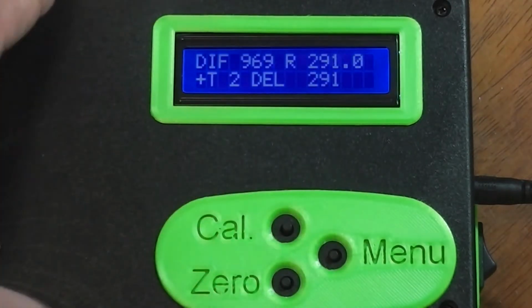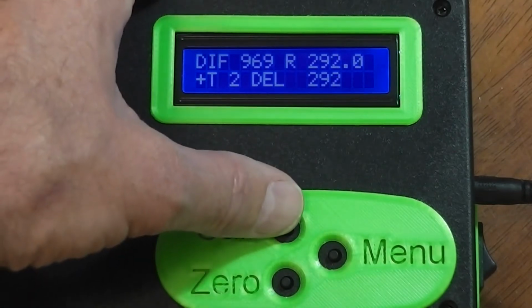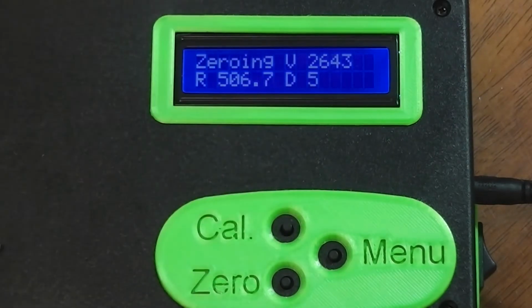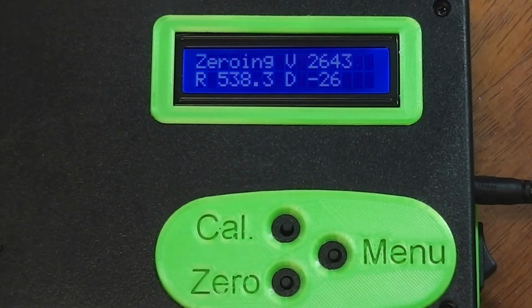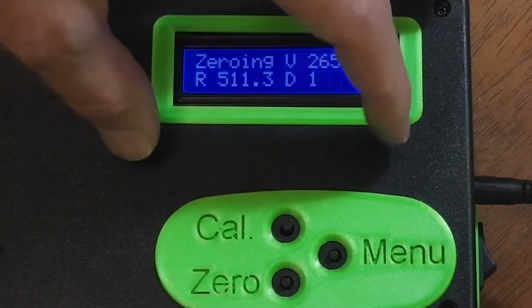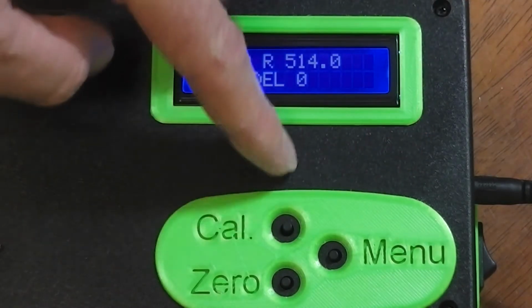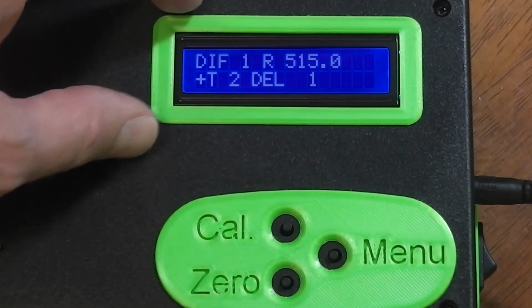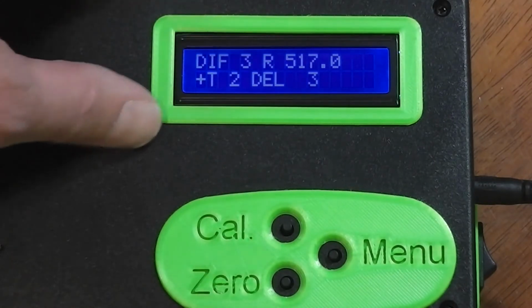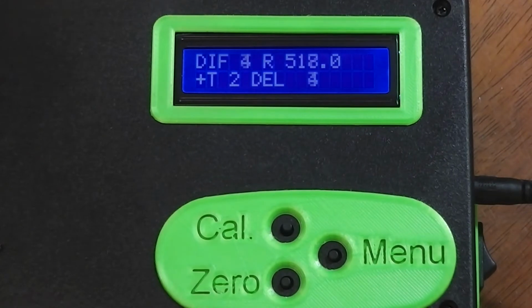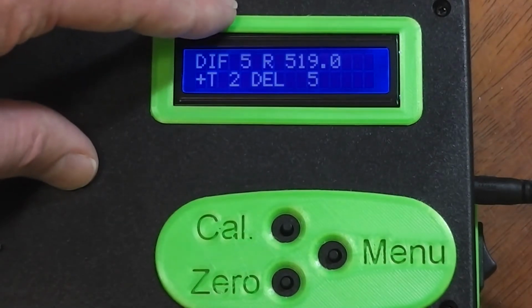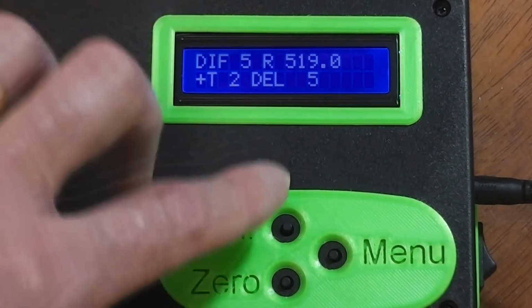Of course we've turned it on, so none of those values mean anything until we've actually calibrated it. So we're going to do that now. Now for this unit, the calibration point is halfway within its meter. So if it has a meter that's here, we want the calibration point to be in the middle, so to speak. Now in terms of raw numbers, that's a number of 510, 512. So that's halfway on the analog to digital converter that forms the backbone of this. So the calibration will move it to that.